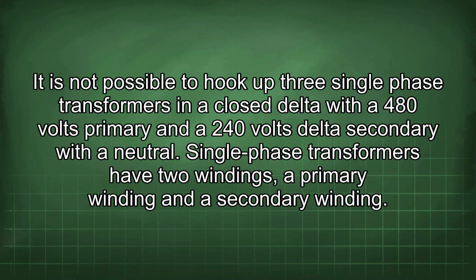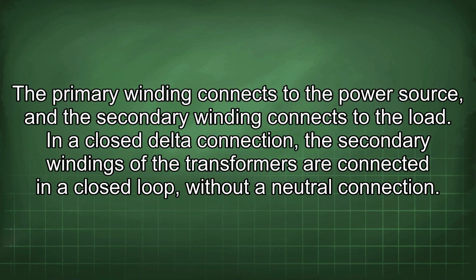It is not possible to hook up three single-phase transformers in a closed delta with a 480 volts primary and a 240 volts delta secondary with a neutral. Single-phase transformers have two windings, a primary winding and a secondary winding. The primary winding connects to the power source and the secondary winding connects to the load.